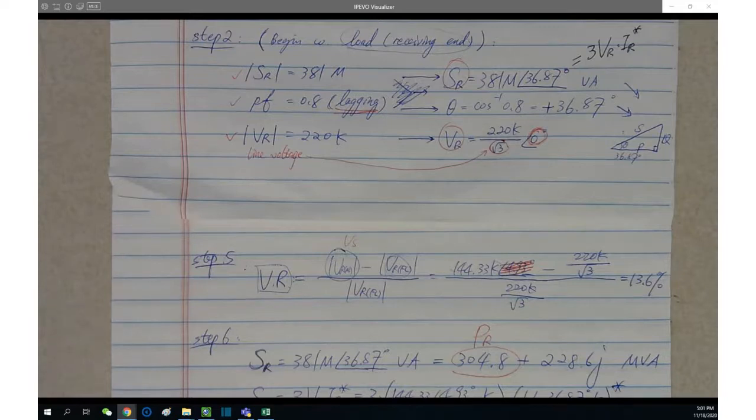I don't know if you have ever seen a power system plant use a lot of capacitor banks. What are they for? They're providing the opposite reactive power towards the inductive load reactive power. It's trying to compensate so that you can bring the voltage magnitude value back up. So reactive power in the power system is related to the voltage magnitude. Okay, remember this.